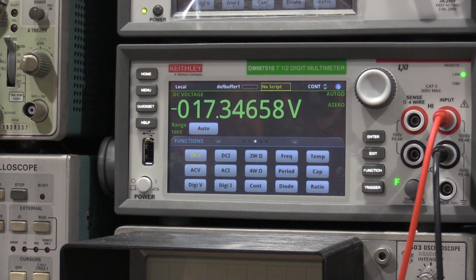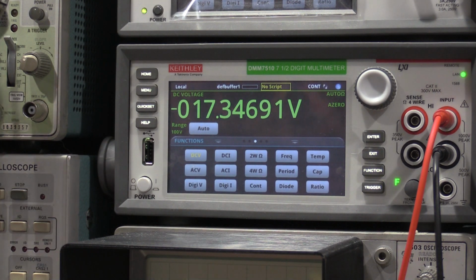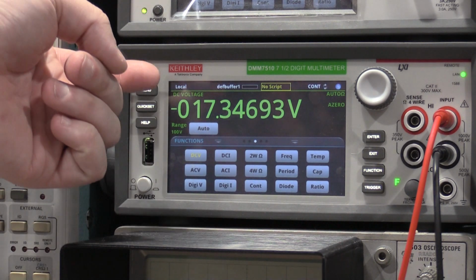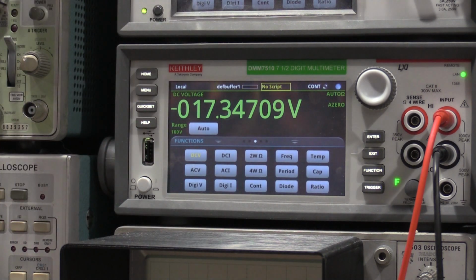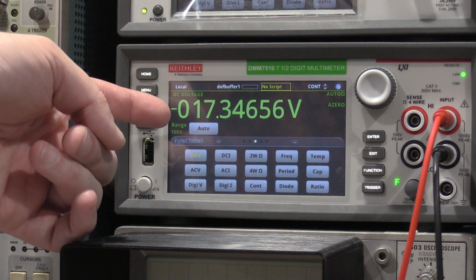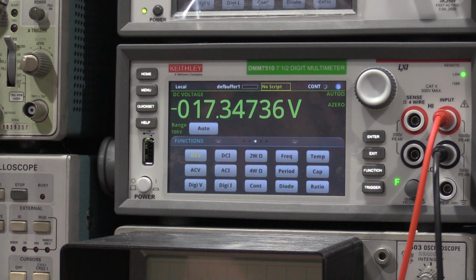As I wind the frequency up all the way to the top of the scale, we're at the bottom. What I'm looking for is this to stay above negative 14 volts, but below 18.89. So if this goes above 18.89, I'll have to adjust C125. If it goes below 14, I'll have to adjust C125, and we'll go from there. So I have to wind up the frequency slowly.